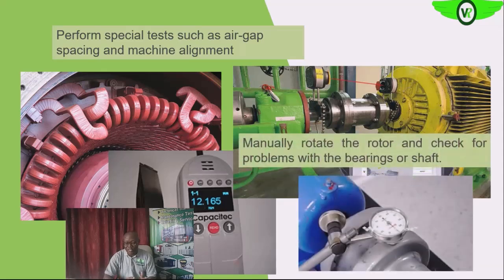We also check the shaft for runout. We can use the dial gauge to ensure that the shaft rotation is uniform. As we are rotating the shaft, once we connect the dial gauge, as you can see, if there is any runout, it will cause deflection on the gauge. So we have what is acceptable and what is not acceptable.